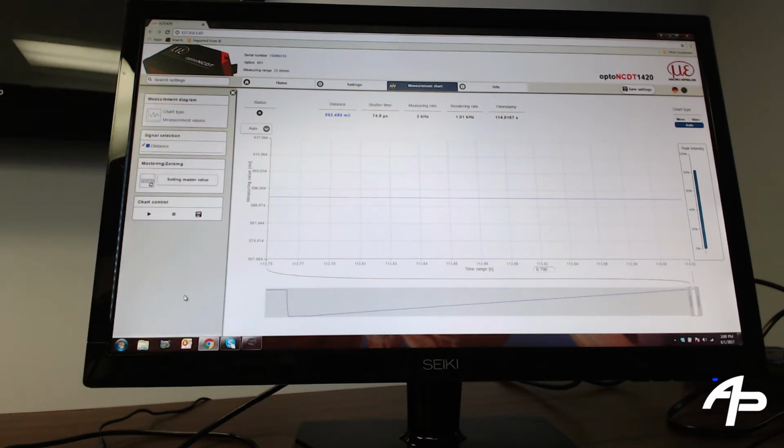So we're going to run it through the scanner once with the same settings as the metal object, and as you can see here, it doesn't come out very well. A lot of lines are squiggly, they aren't correctly reading the object, and it would get a different random reading each time. This would not be good for something that needed to be measured because the measurement isn't accurate, and it also wouldn't be accurate each time.